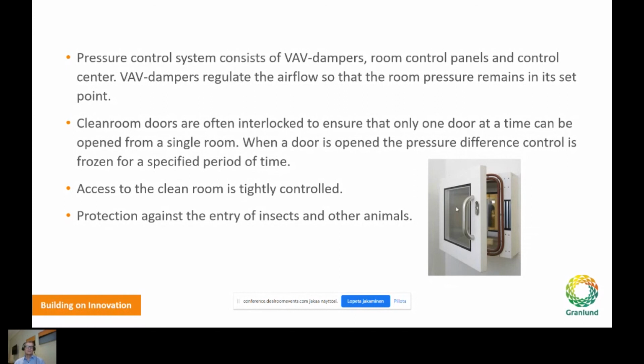Clean room doors are often interlocked to ensure that only one door at a time can be opened from a single room. It's possible also to do it by traffic lights, but normally an interlock system is more sure for conditions. So when a door is opened, the pressure difference control is frozen for a specific period of time, and access to the clean room area must be tightly controlled.